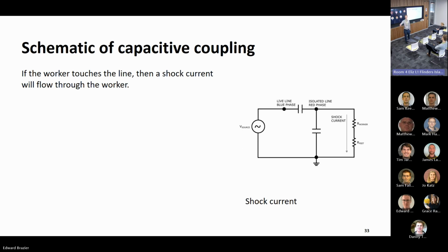When you earth the circuit conductors at the work area, so that your working earths are within line of sight from where you're working, in that case it does short out the capacitor you can see there from the isolated conductor to earth.